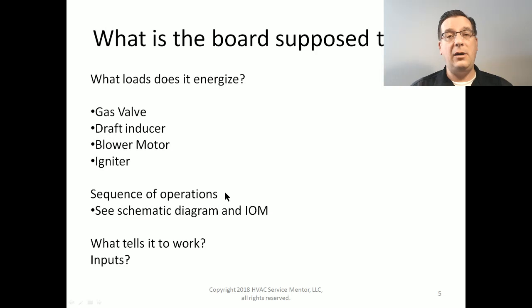And how do you know what the sequence is supposed to be? Well, that can be challenging. You will find it in a combination of the schematic diagram for the unit and the installation and operations manual, also known as the IOM. Every IOM for every piece of equipment has a section called Sequence of Operations. And if you read the sequence of operations, what you are reading is the step-by-step operation sequence of that electronic circuit board. Once you've identified that, or if you at least have a pretty darn good idea, for example, if it's a gas furnace, it works the same way most gas furnaces do, you have a pretty good idea what that sequence is supposed to be.